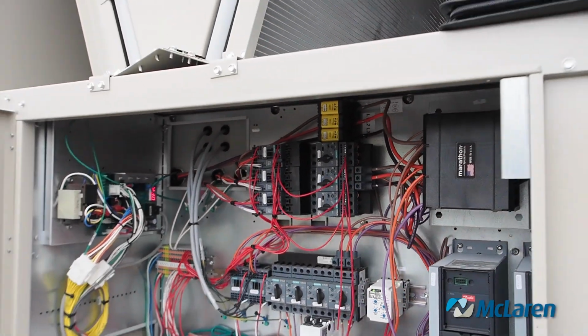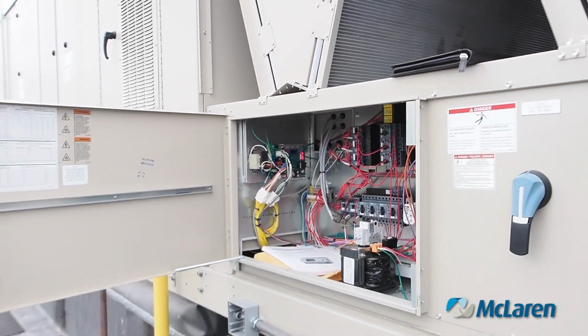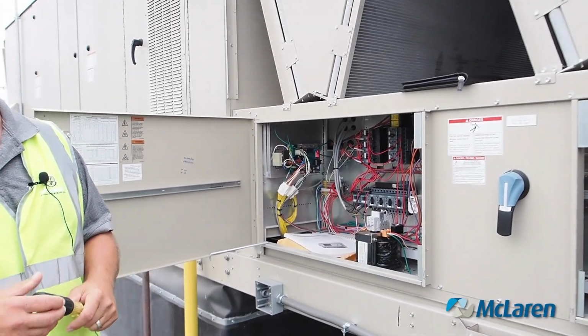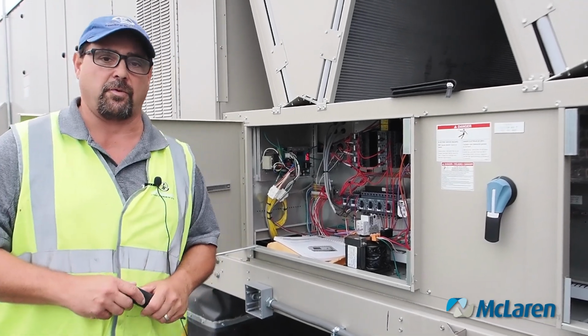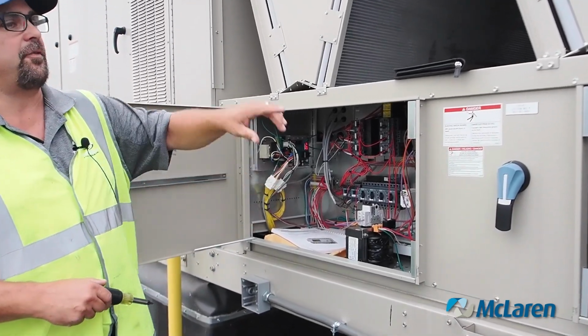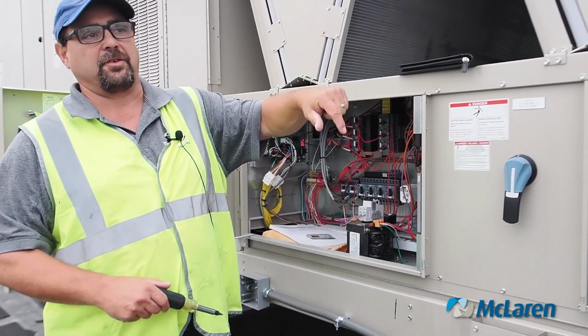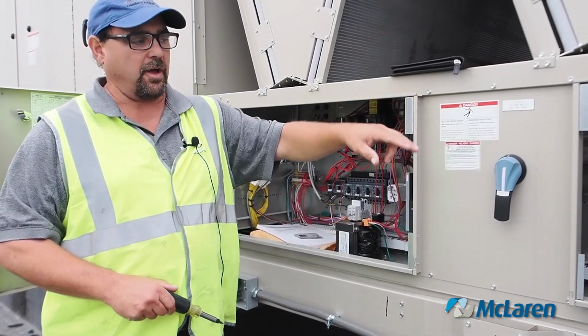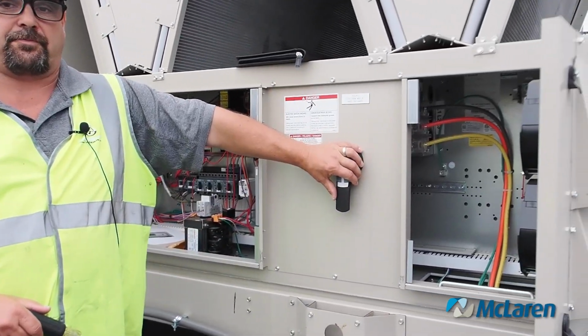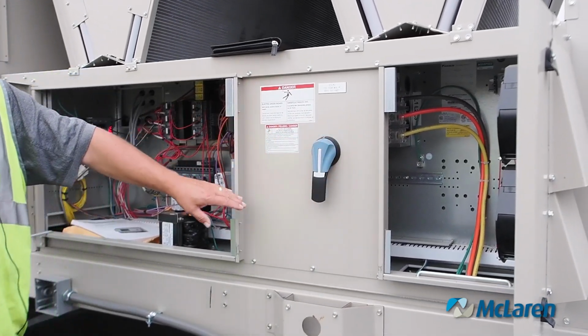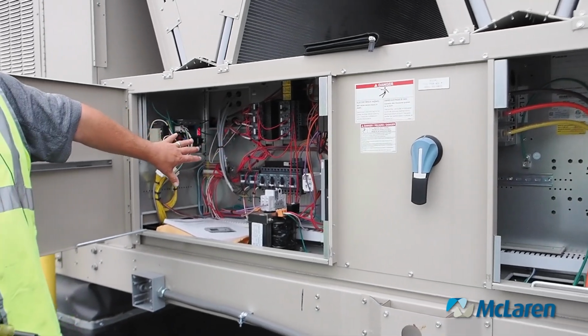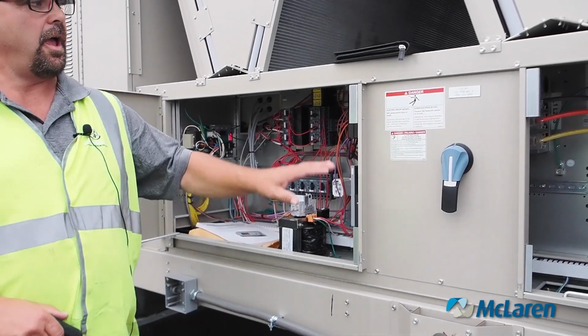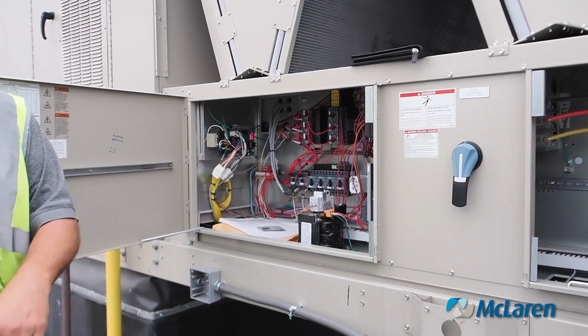You could cause a problem if there's a short, if there's anything that causes that to trip. Doing it live is not the safest way to do it. And this panel here, after you shut down through the building management system, confirm it at the control side, then you would shut your disconnect off here, lock out, tag out, and check out all your electrical connections in here and in the compressor section. We'll get to that in a minute.